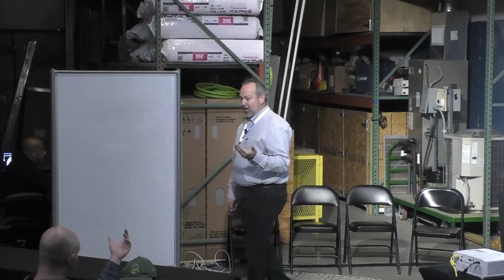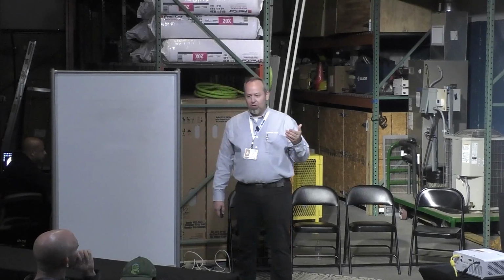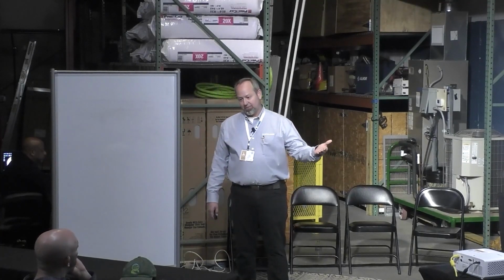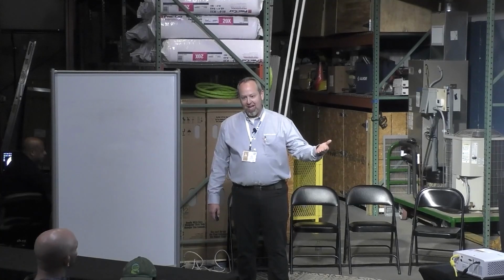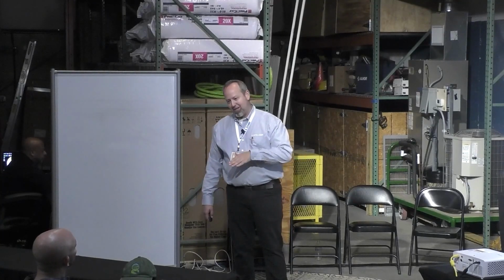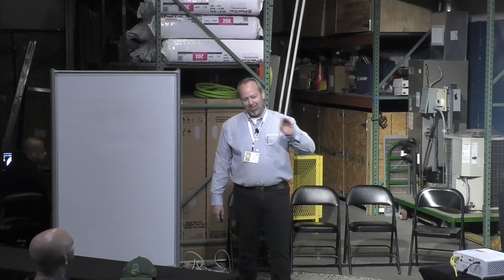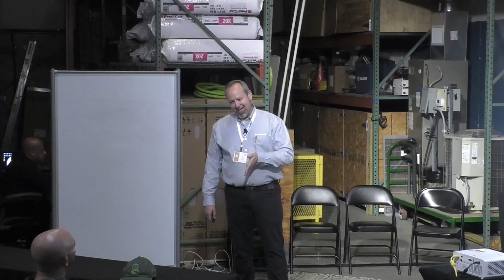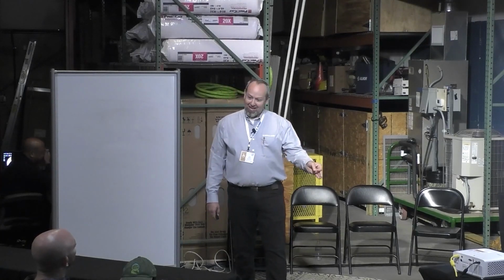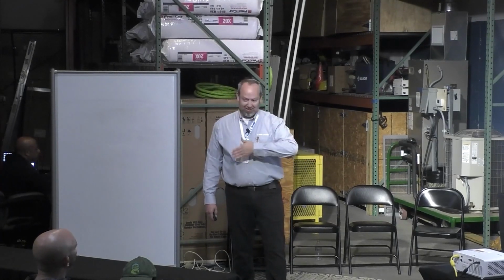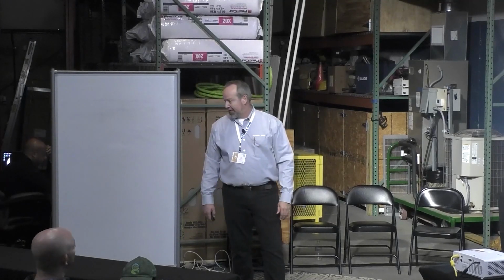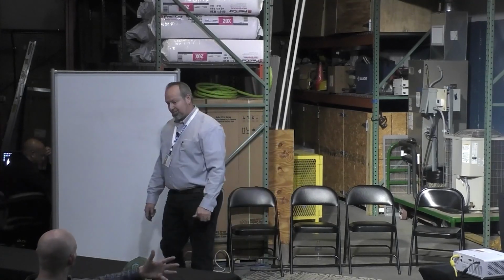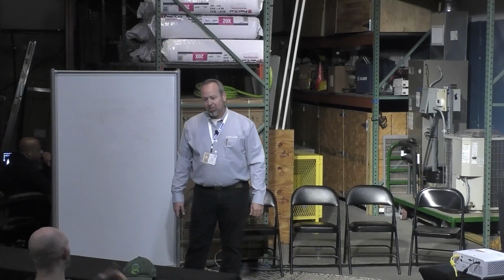So the comment, and I'll repeat it here, is that it would be the logic in the defrost board that would be able to know that it's going to check for defrost. The challenge with that is, depending on if you're time defrost or demand defrost. If you're time defrost, then you can push that timer in there. If you're demand defrost, then it's going to check, and if it doesn't need defrost, it's going to pass and can continue to run. And so for defrost, it waits 15 seconds, and then it sends a call to the W, waits 15 seconds. Correct.